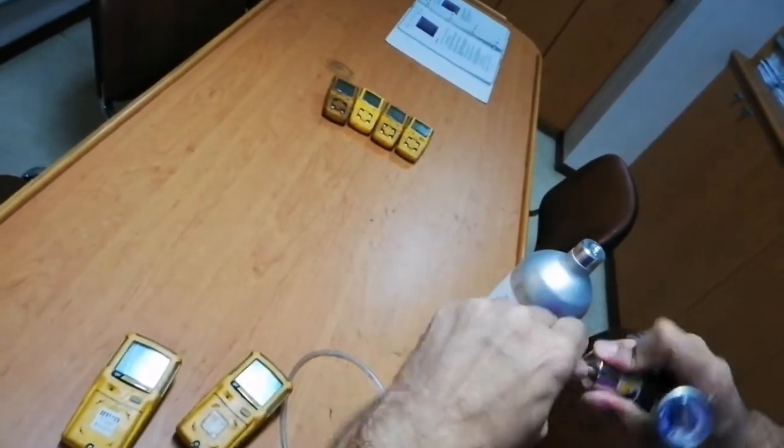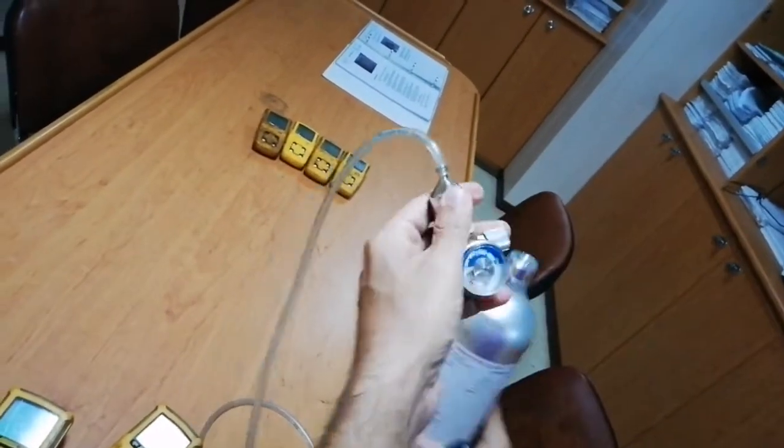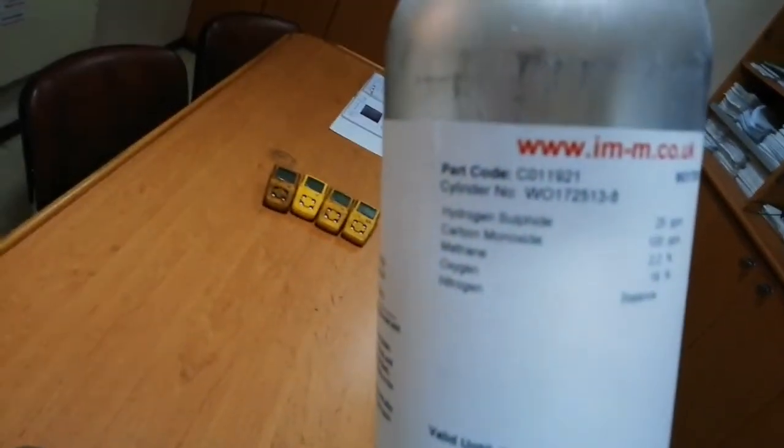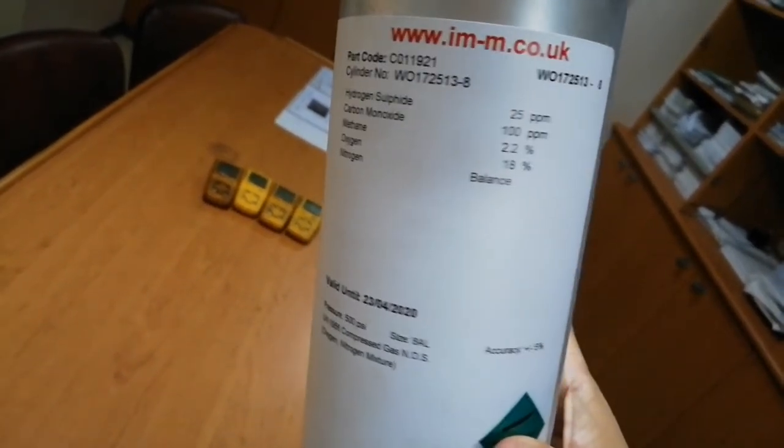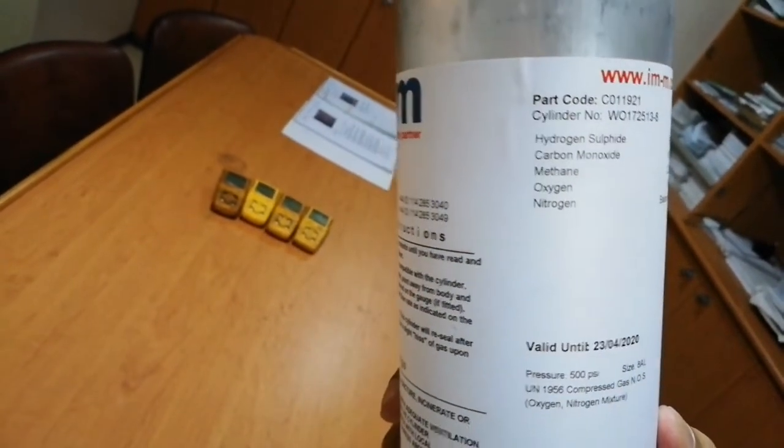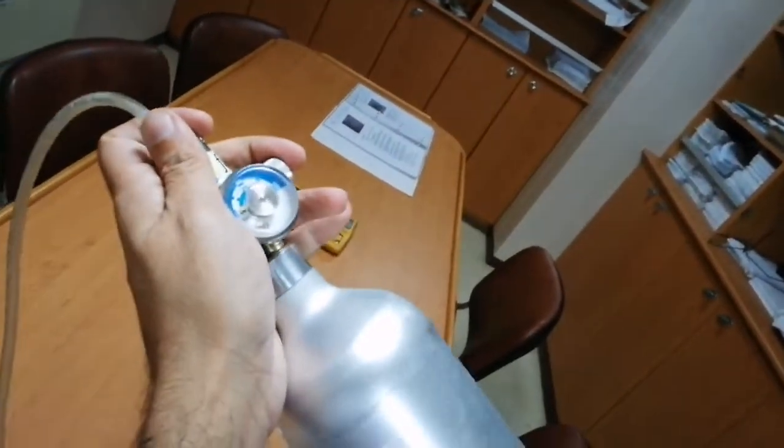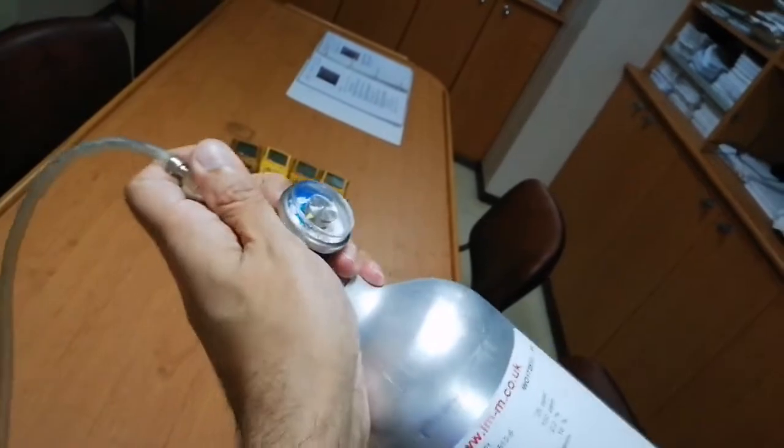We'll fix the regulator to the span gas cylinder. This span gas cylinder contains hydrogen sulfide 25 ppm, carbon monoxide 100 ppm, methane 2.2 percent for measuring LEL, and oxygen 18 percent. All balance is in nitrogen.